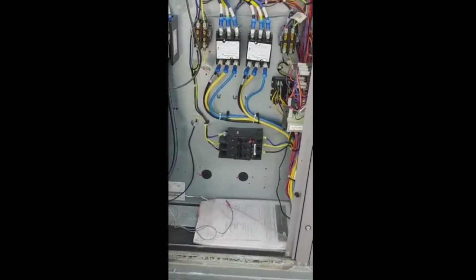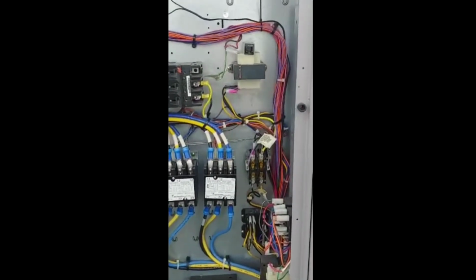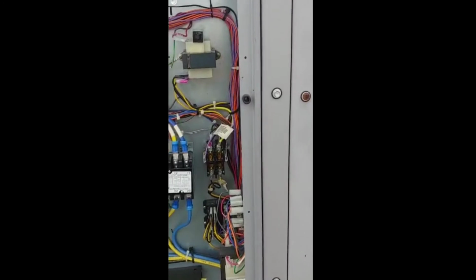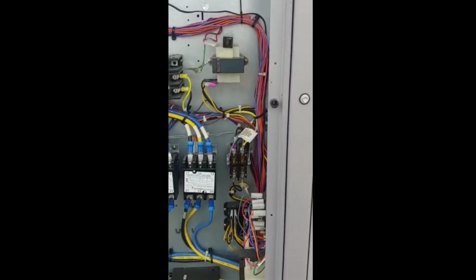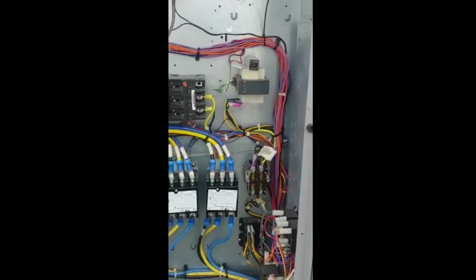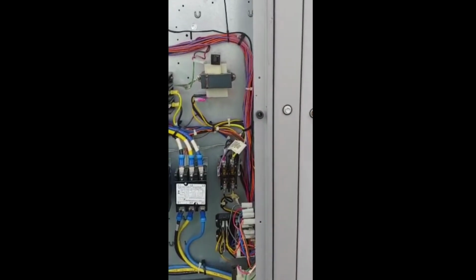Over time they were rubbing and created the problem, so pretty much that was it. It took me a little time because I had to follow all the wires, but most of the time it's due to vibration, and usually it's by those pressure sensor switches because they don't really anchor those wires - they're just dangling there. With the variation of hot and cold, the plastic gets brittle, and over time it will normally cause that problem to happen.